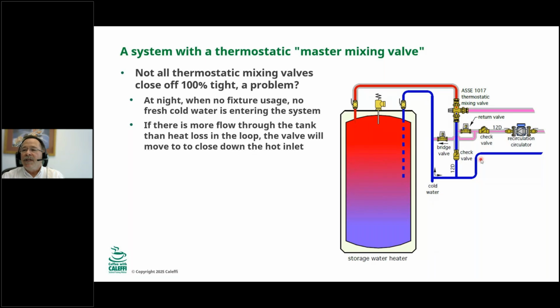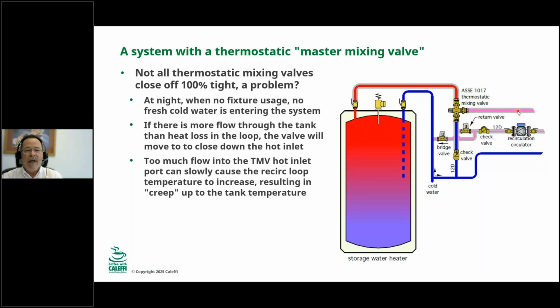So this recirculation water is coming back. It's going into the cold inlet of the valve. It's also going over here into the tank. Now, if this hot port on the inlet of the thermostatic mixing valve doesn't close tight, you're going to have a little bit of water going into the tank, out here, and going back and coming into the mixing valve. So it can happen that if there's more hot water flow, if there's more BTUs leaking through this valve than you're giving up to the atmosphere in your system out here, the whole loop will heat up. Okay, the whole loop will heat up, and that's called temperature creep. So too much flow through the tank into the valve and out will eventually cause creep. And in the morning, when someone opens up a fixture, they're going to get a blast of hot water. So how do we do that? What do we do to fix that?